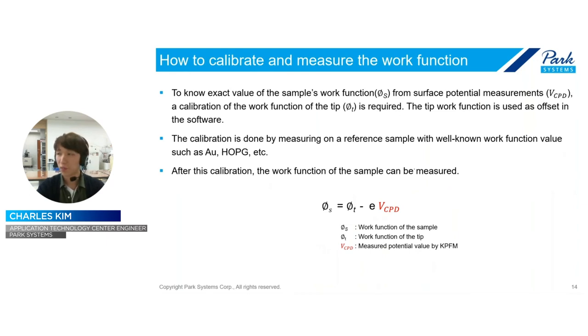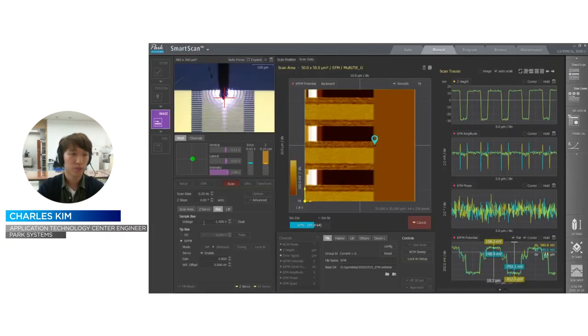And the last topic is calibrating the work function. Previously, I said there is a small offset. That offset comes from the cantilever work function. So to compensate this value, we need to measure some sample whose work function we already know. If we already know the work function of the sample, then we can use it as a reference.